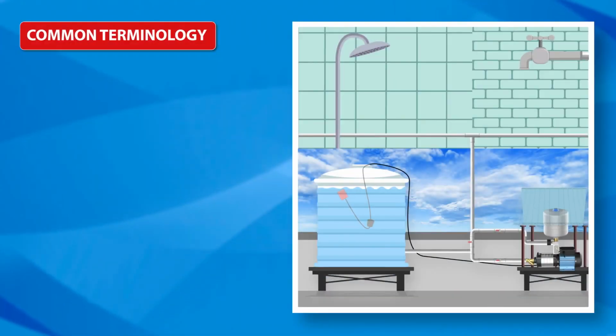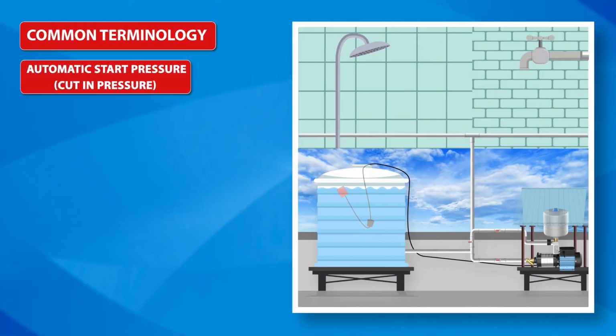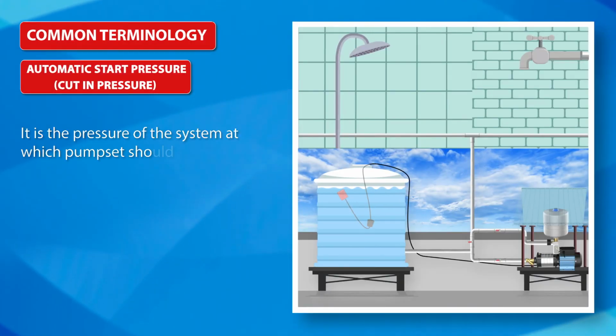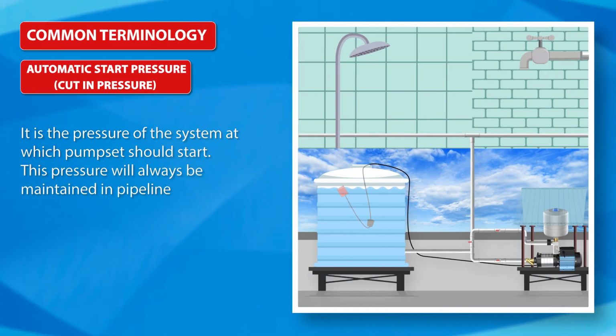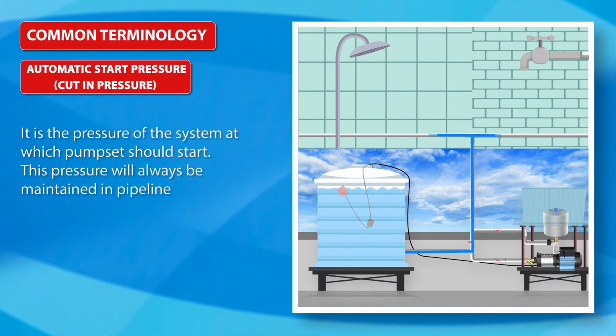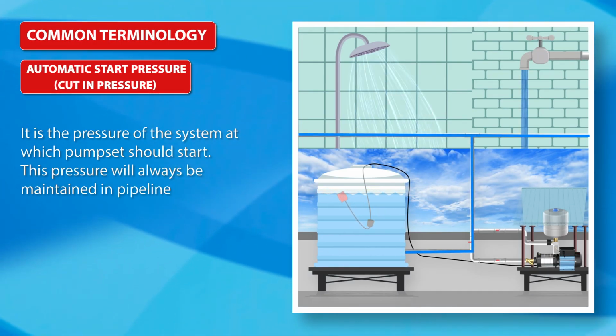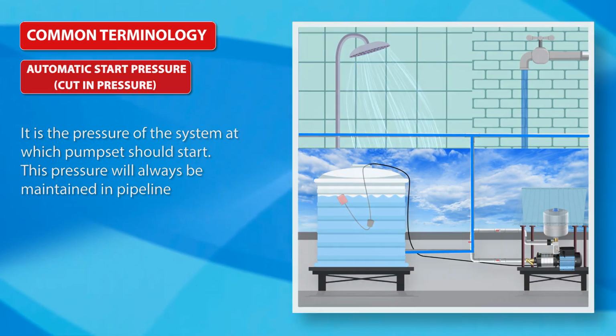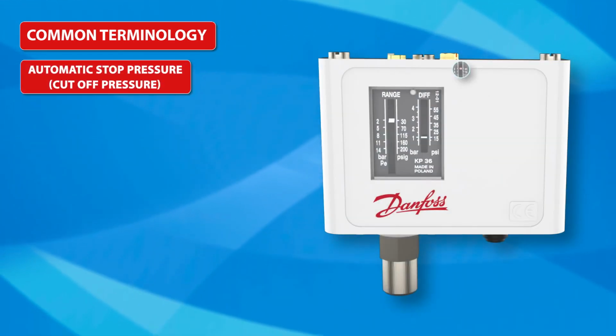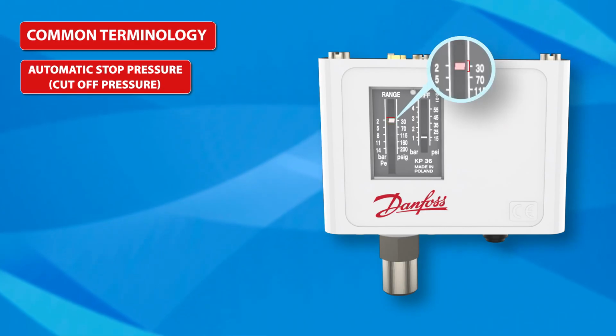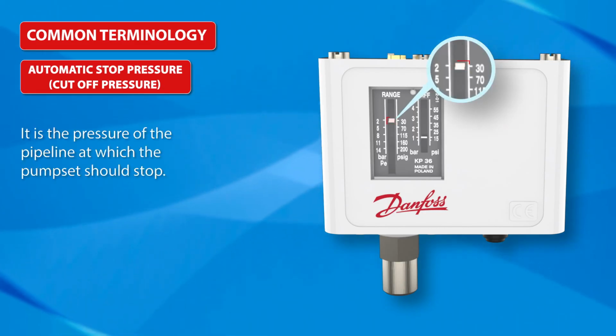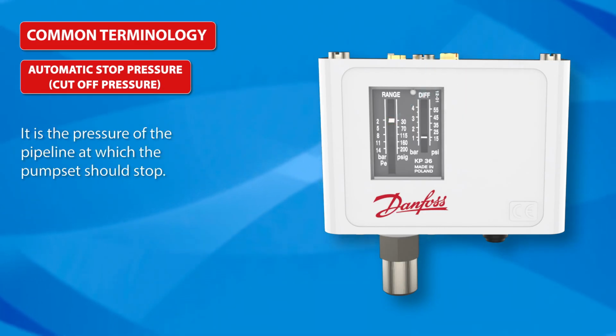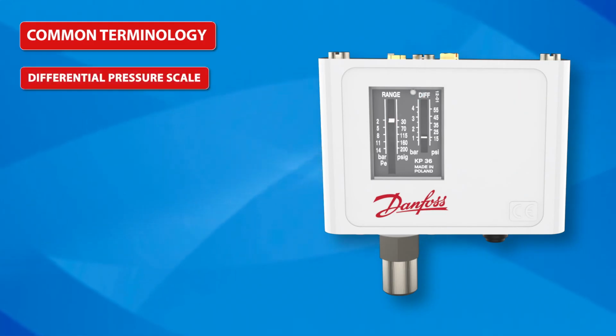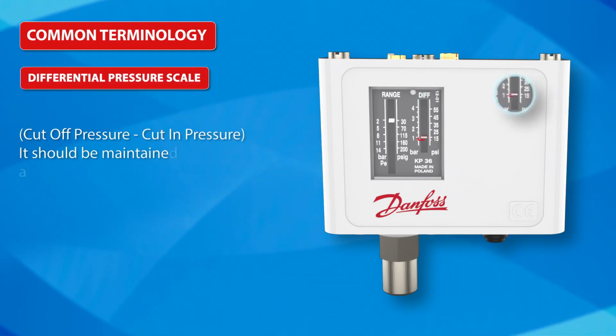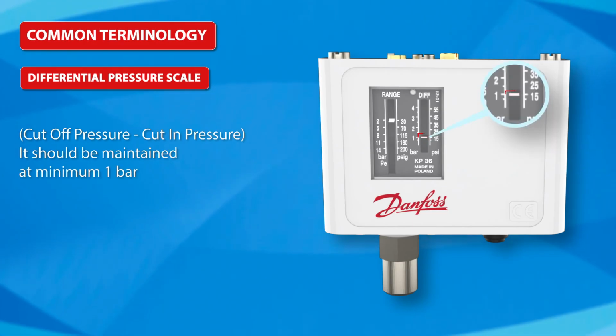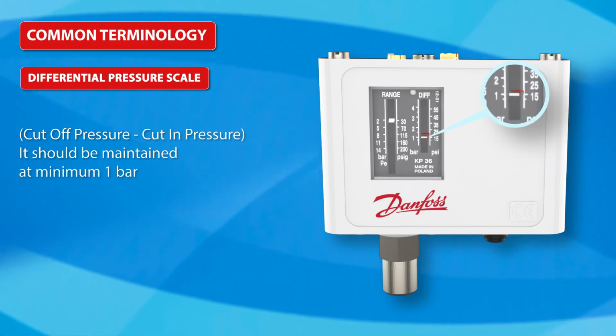Common terminology: automatic start pressure or cut-in pressure. It is the pressure of the system at which the pump set should start. This pressure will always be maintained in the pipeline. Automatic stop pressure, also known as cut-off pressure or range, is the pressure of the pipeline at which the pump set should stop. Differential pressure scale is cut-off pressure minus cut-in pressure, and it should be maintained at a minimum of 1 bar.